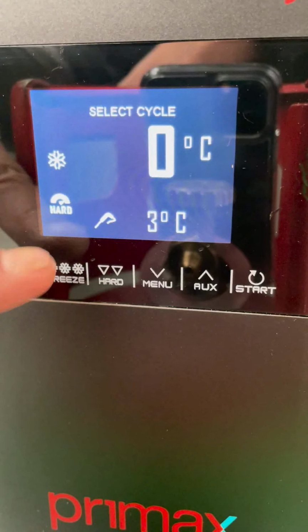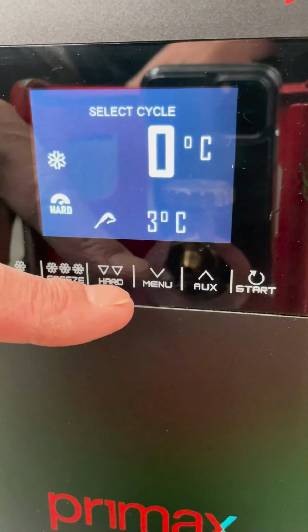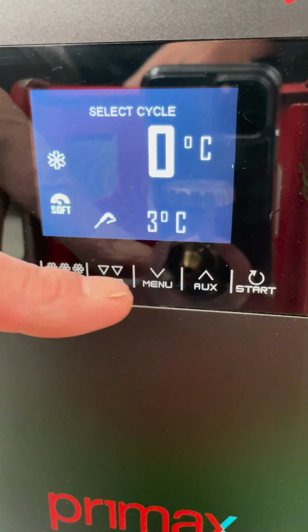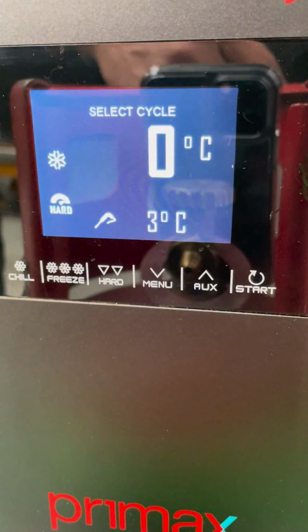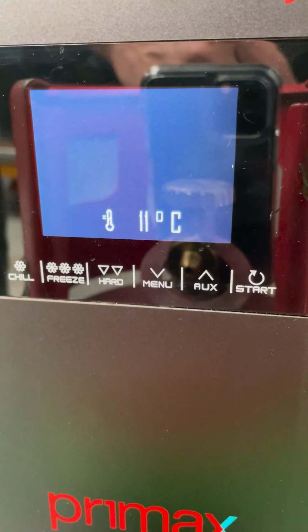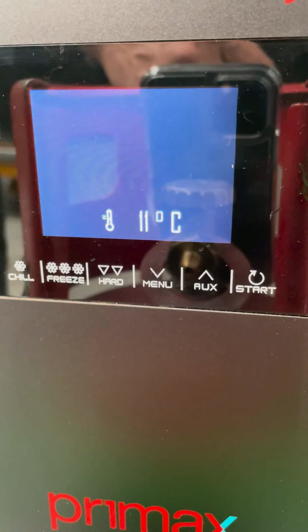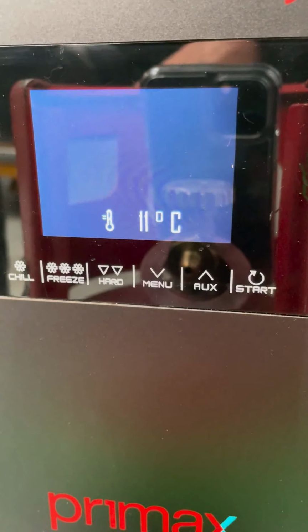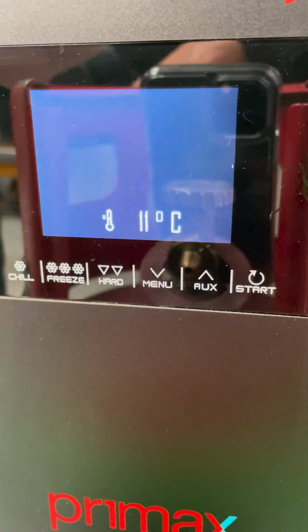But there is also blast chilling hard. You see, you just switch using this button. You have blast chilling hard, which, as in the BF line, allows you to save time. How? By using in the first phase, when the product is warmer, a more aggressive air temperature, which can go even to -20 for the first phase. In the second phase, the machine will go on less aggressive temperature, so delicate air temperature around 0, until you reach 3 degrees in the core, or until you reach the 90 minutes countdown.